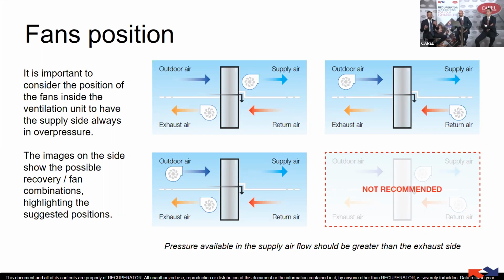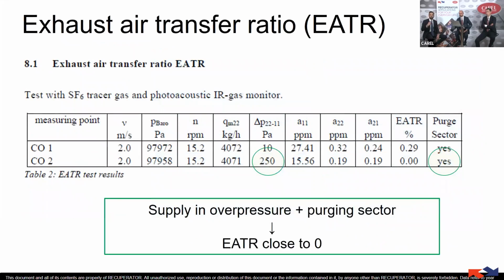This is, we have seen, mainly the theory, but making the test, what are the numbers that we're talking about? If we have the supply side overpressure of 250 Pascal, the circle green on the left, we have the purging sector that is properly installed and also well designed. Then we can have EATR, that means exhaust air transfer ratio, that is a contamination, equal to 0. 0 is the same number as the plate heat exchanger. If you look above, you can see that the EATR could be a little bit higher with a lower pressure difference, but even then a really low value. So this is really, really important. 0 is a very impressive number.